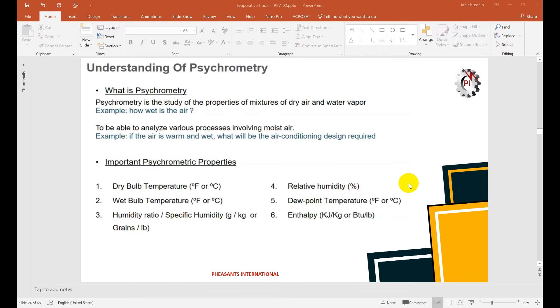The humidity ratio is the actual grams of water vapor — the actual moisture — expressed in grams per kilogram of dry air. Relative humidity is the actual moisture available in one kilogram of dry air versus how much moisture the air can hold at a saturated condition at the same temperature. The dew point temperature is the temperature at which saturation is reached, where no extra moisture can be added — any additional moisture will condense.